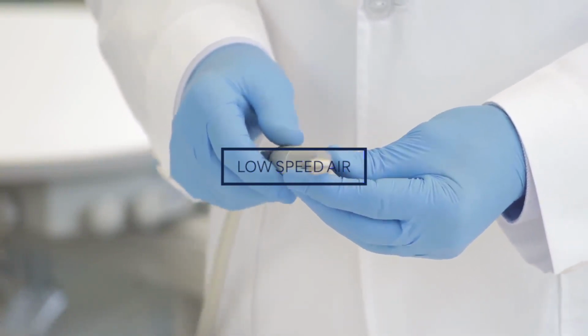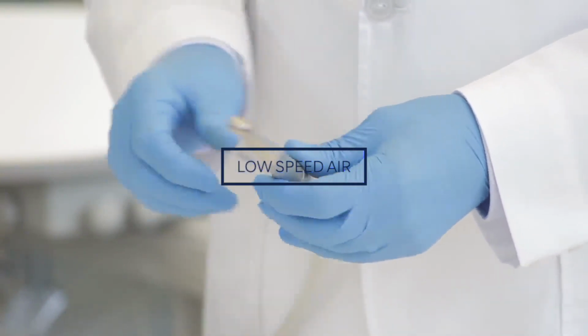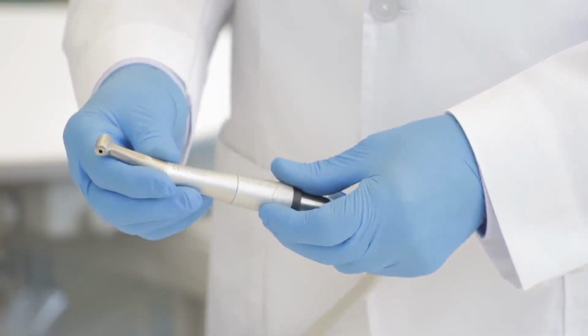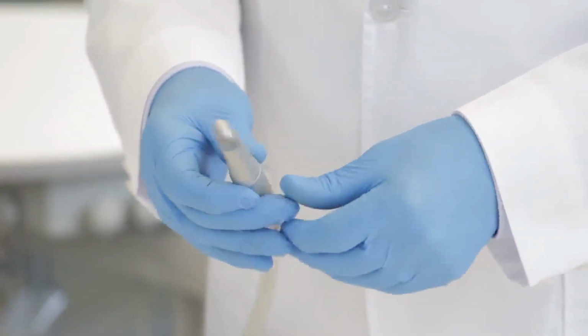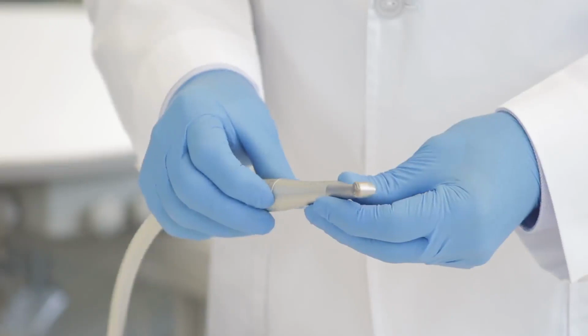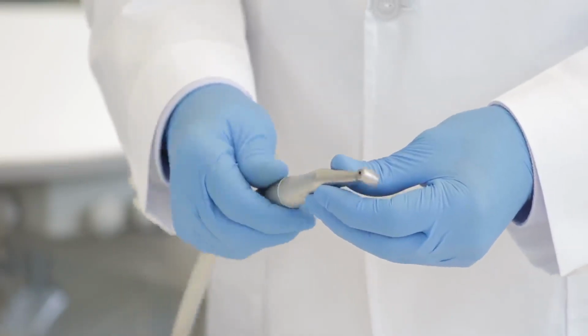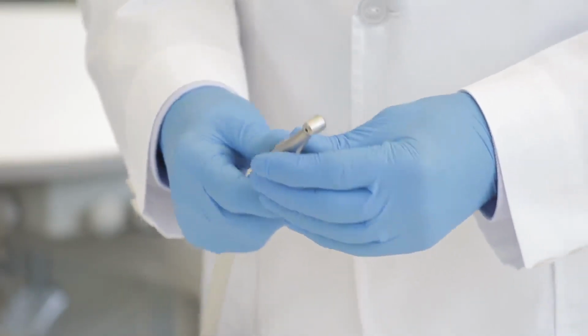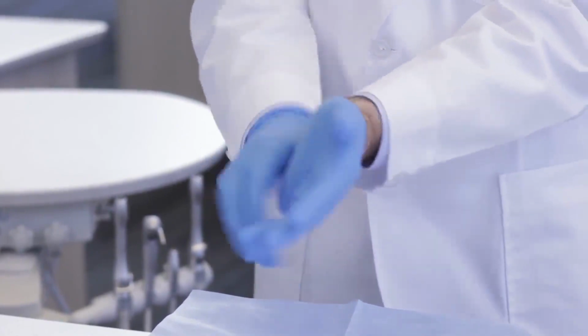Reprocessing instructions for low-speed air-driven handpieces. Clean and lubricate the handpiece as soon as possible after treatment. Failure to properly maintain the handpiece may cause contamination, leading to infection, product failure, or overheating, leading to possible burn injuries. Always use personal protective equipment before the process.